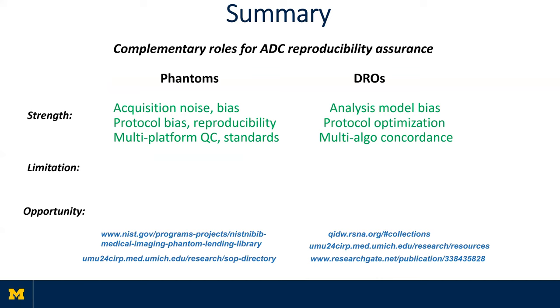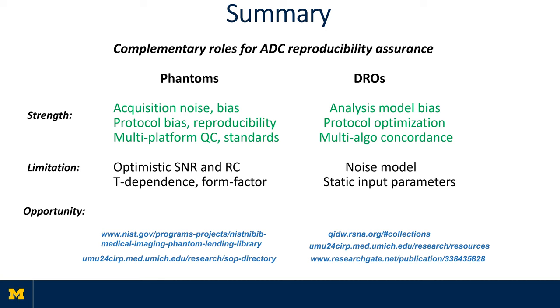In summary, we find that physical and digital phantoms play complementary roles for improving ADC reproducibility. Physical phantoms help hardware and acquisition protocol evaluation and measure realistic noise, while DROs facilitate testing image analysis pipelines and biophysical model bias. The challenges are that physical phantoms provide unrealistically good SNR and are more costly to manufacture with specific form factors to fit different coils. While DROs require a noise model and use static input parameters, they allow virtually infinite model complexity. The desired improvements are in representing combined system parameters and biophysical models in a single physical phantom — this is where the field is moving now — and in providing DRO engines.